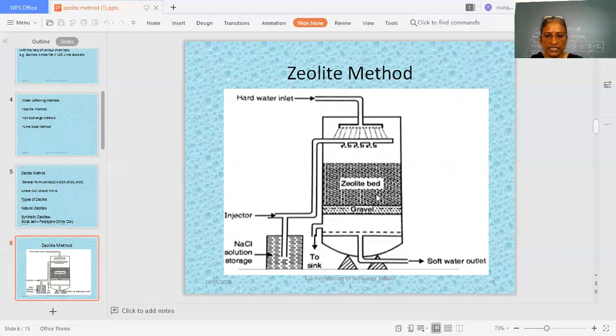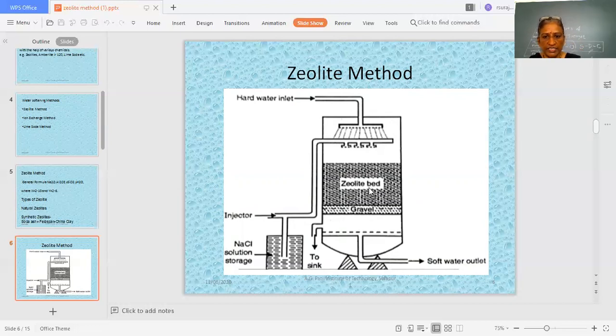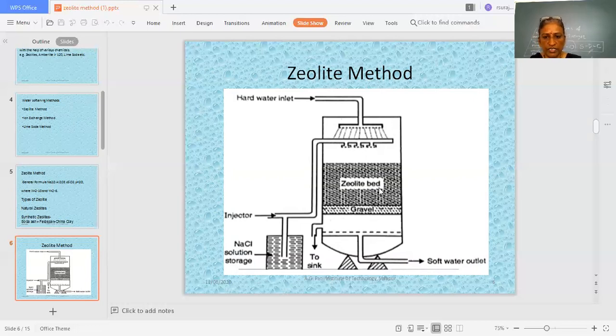This diagram explains how the zeolite method is carried out. The hard water inlet is at the top of the tank. The zeolite bed is present, and some coarse gravels are spread near the zeolite bed so that whatever suspended materials are there, those are trapped in the gravels. When the water passes through the zeolite bed and is kept in contact for some time, the calcium and magnesium ions are captured and replaced by sodium. The remaining part reacts with sodium and that salt is given out in the water. The hardness-causing Ca²⁺ and Mg²⁺ are removed.